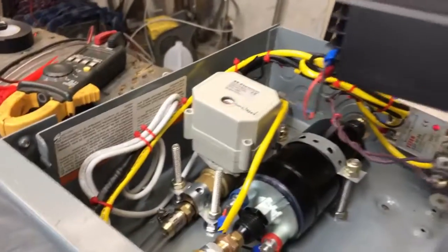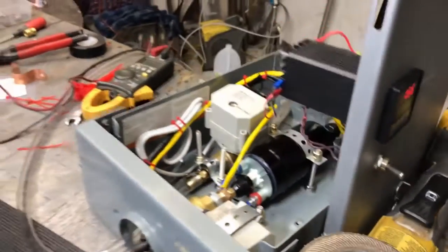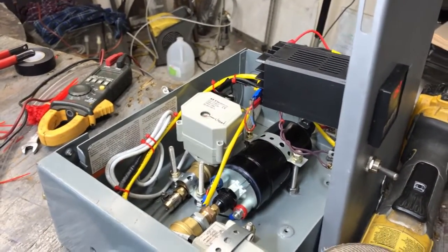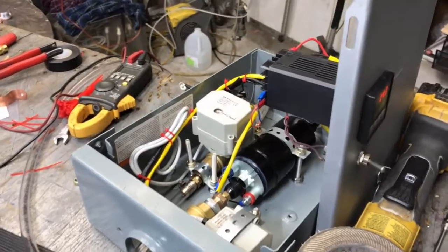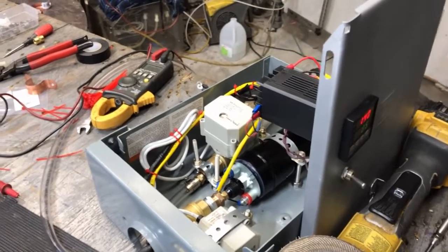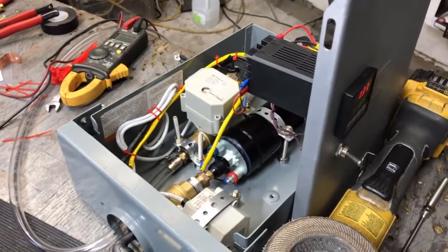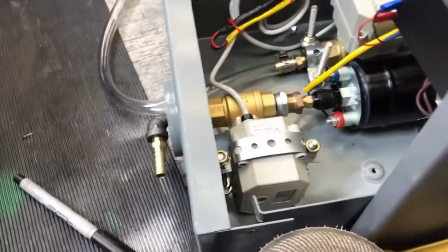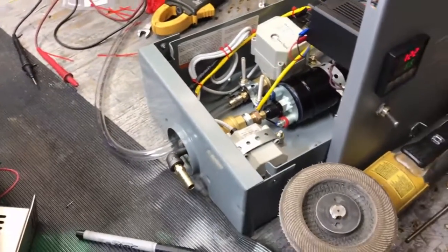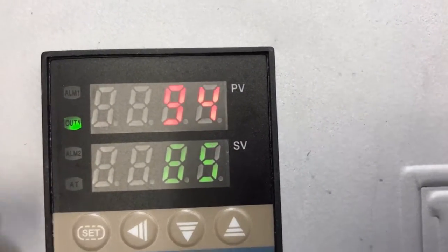I still haven't got to the bottom of that. Later down the line, a jumper takes away that stray voltage long enough for these valves to kick on. I think there are capacitor-type batteries inside these pumps that use 125 volts AC to charge a capacitor during power-on, then when power is cut, the capacitor discharges by running the electric motor for the servo valve — very small, low-power electric motors, similar to those inside a cassette tape player.